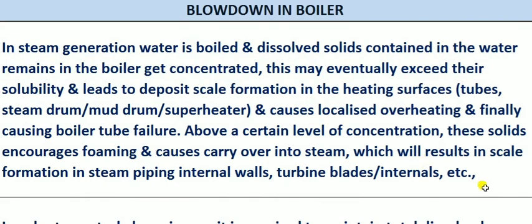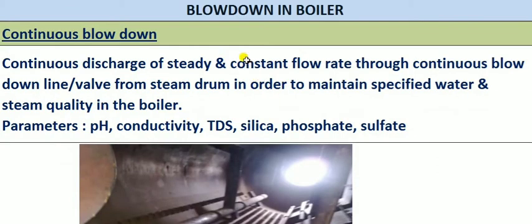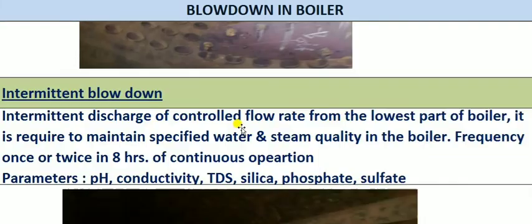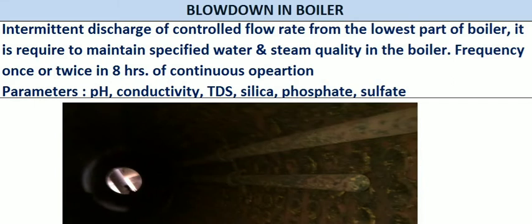So now it should be clear. We know the importance of blowdown operations — to maintain water quality as per standards, to avoid scale deposition in boiler tubes and outlet pipelines. It should be optimum to avoid excessive energy losses. The two types are: continuous blowdown, which is kept continuously open at a certain valve opening from the steam drum; and intermittent blowdown, taken from the lower part of the boiler — the mud drum — operated for a certain time, typically two to five minutes, then closed.